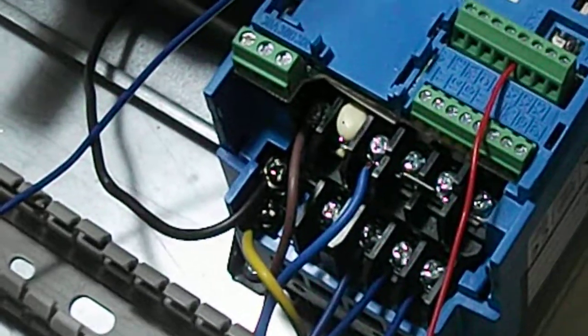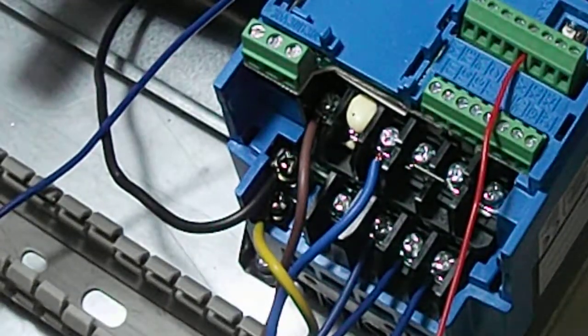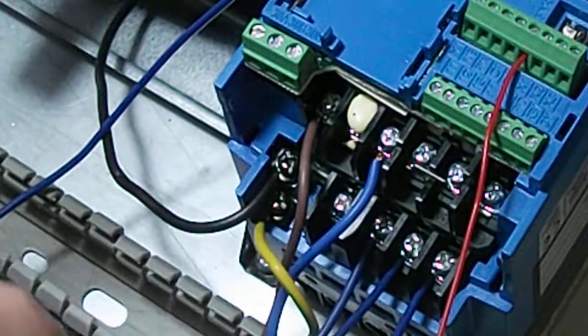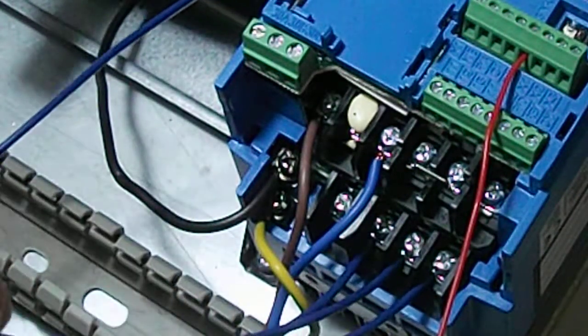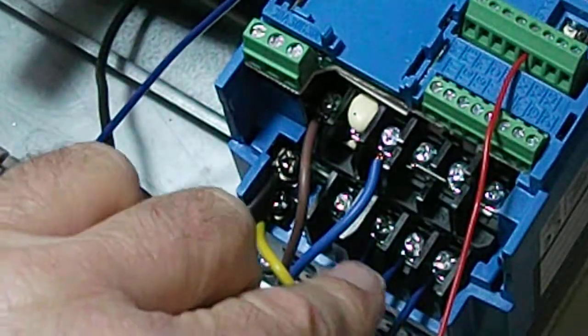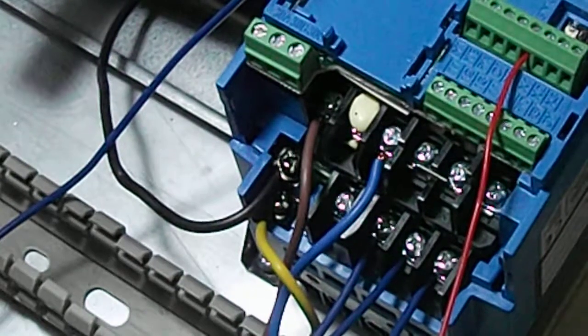If we zoom in there a little bit, you should be able to see I've connected live, neutral, and earth on the inputs, and the three phases are coming out here on U, V, and W at the bottom, and they're going to the motor.